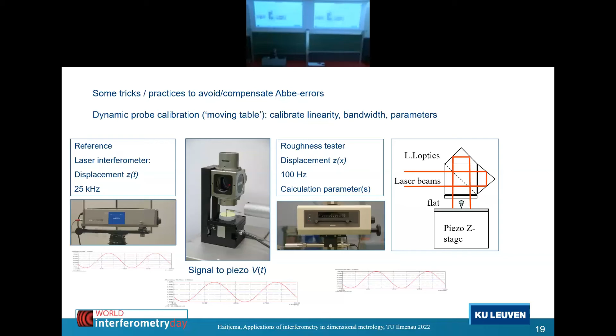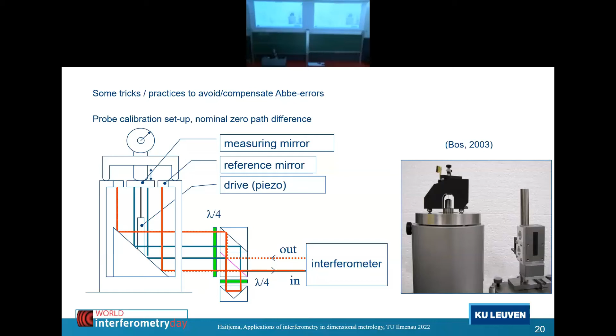Then, talking about probe calibrations, this is another trick, to have a folded beam, and in the end the probe is calibrated also in a way that satisfies the Abbe principle, because here you measure just the displacement as a sum of these two, and this is the reference beam, so you have basically zero path length difference. And here, where the interferometer is put, there's a bit of air, which should not be there, it's better not, but in principle it's all compensated.